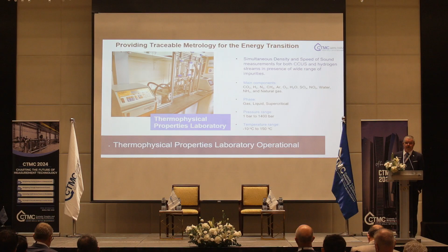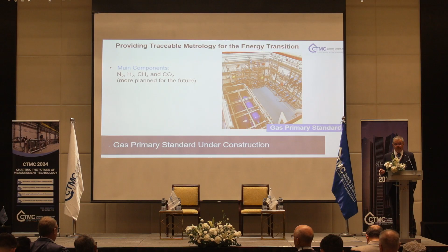Now, I showed you earlier the gas primary standard. I just skipped over it in terms of hydrogen. But we're also building at NEL a gas primary standard. The main components will be nitrogen, hydrogen, methane, and CO2. That's initially; we can swap out these components. Obviously, we think the main interest will be CO2 and hydrogen for the CCUS and hydrogen industries. More are planned for the future. Basically, if it's safe to do so, we can fill this rig with multiple components of gas. So we can get something like a calibration gas that you would get for a gas chromatograph, with a particular set of contaminants, and use that rig. So we're hopeful that that's going to be really useful for our customers.